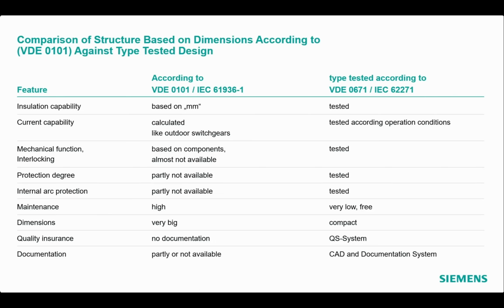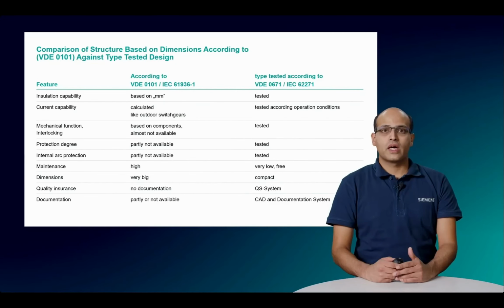Similarly, current capability is calculated based on current flow, conductor cross-section, etc. This also meant that the dimensions of former switchgears are very big in comparison to the compact design of current days. Today, switchgears undergo type testing in accordance with IEC standards, ensuring the design meets the requirements specified in IEC 62271, for example, in the form of dielectric tests and temperature rise tests.